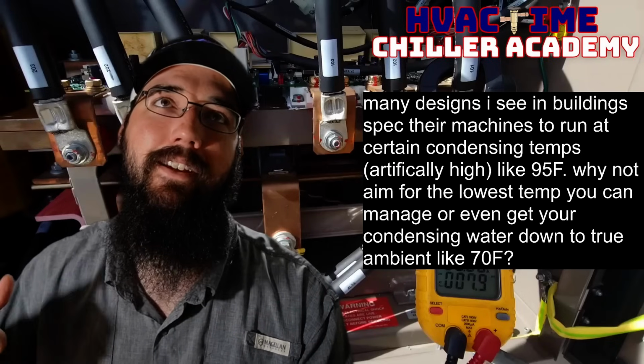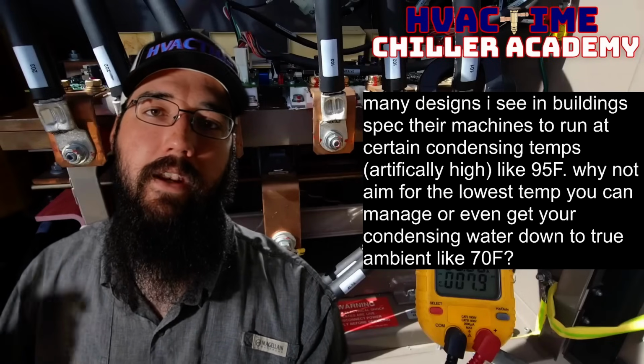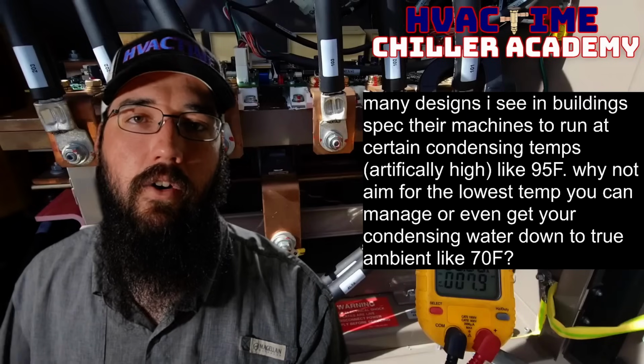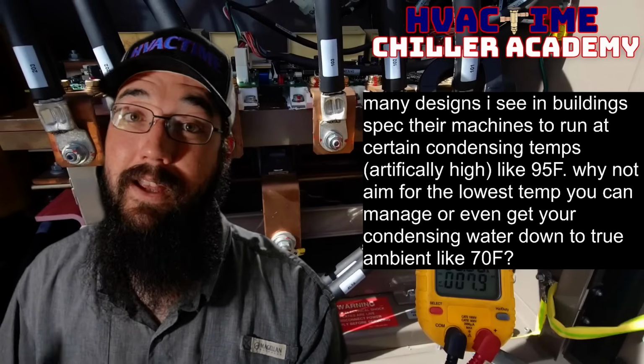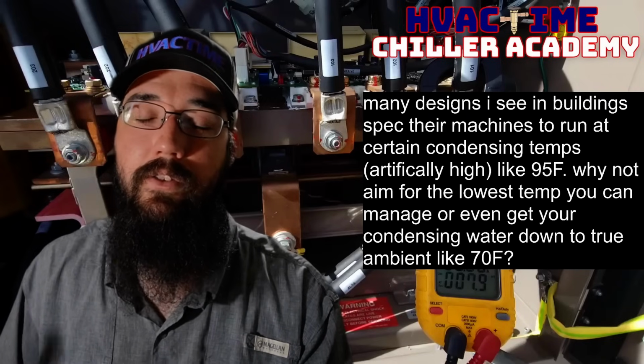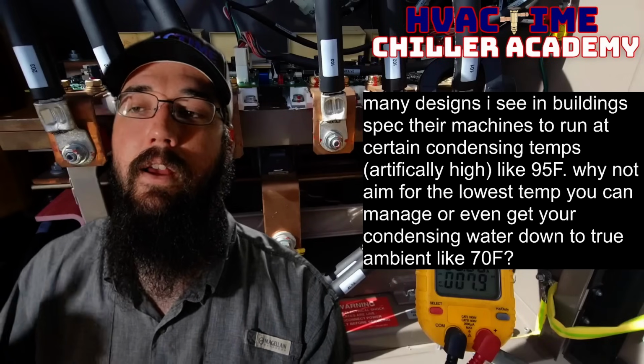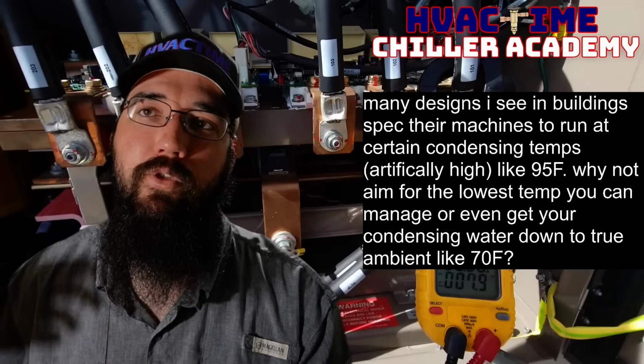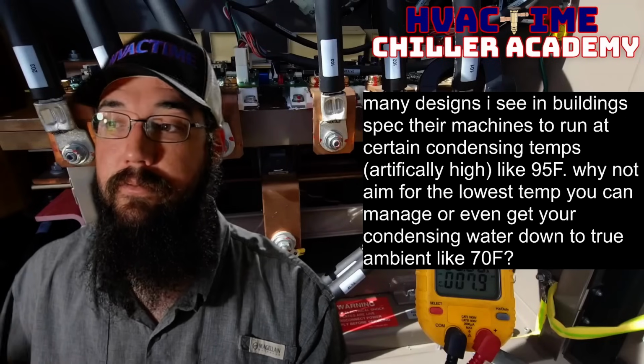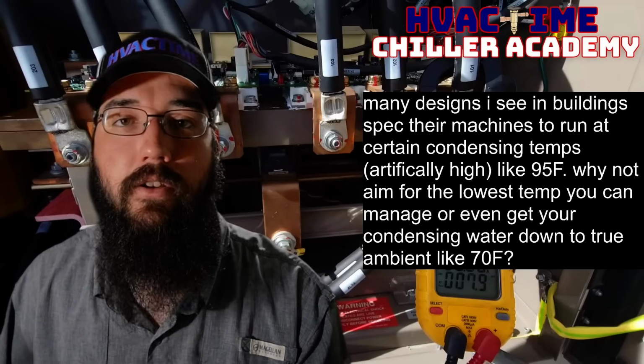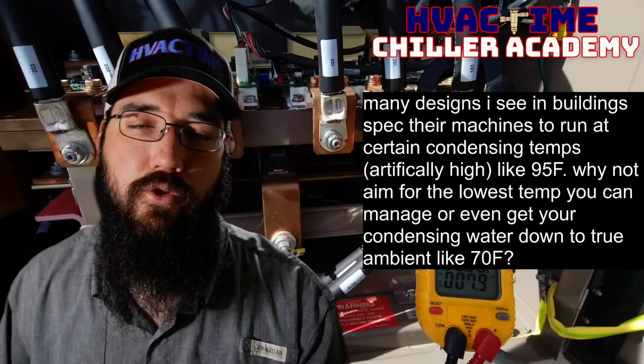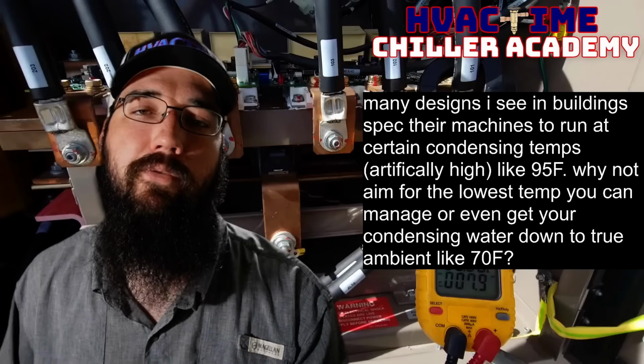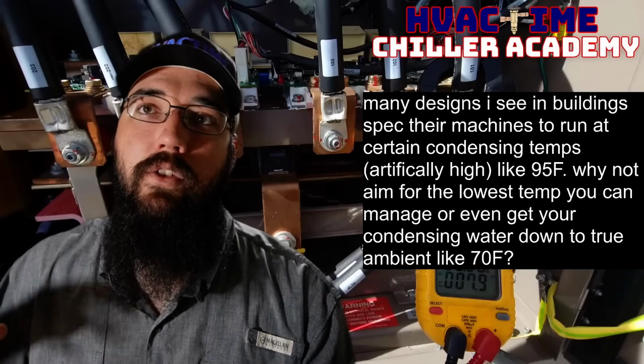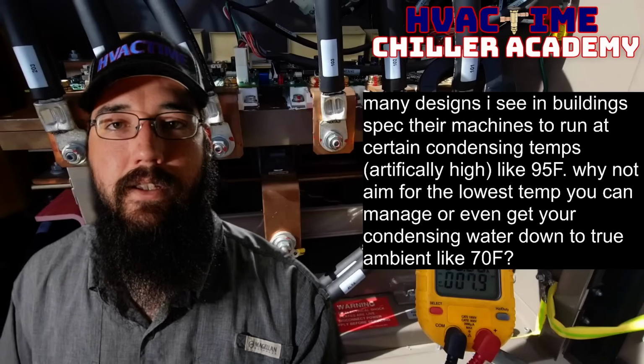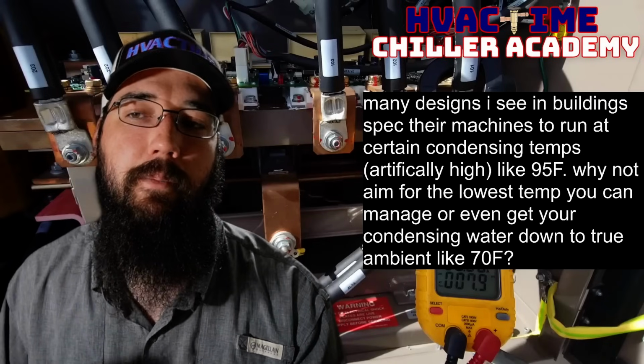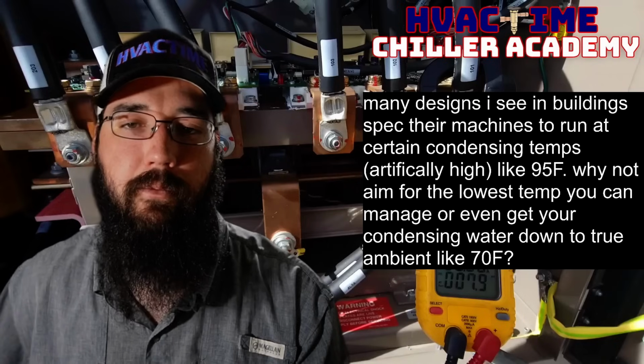And all it takes is a temperature sensor and a relative humidity sensor on the outdoors tied into the control systems. And most control systems nowadays, especially just your regular PLCs, programmable logic controllers, so you're talking your Honeywells, your Distechs, your Johnson Controls, your Trane, all of these have basic control algorithms already built out for variable condenser water control. So once you have just the temperature sensors, it's not that hard to integrate the PID required to control this, the algorithm that we need.